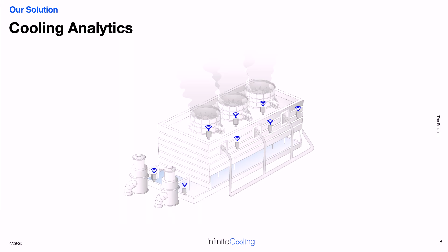We're addressing all of these issues in a couple of ways. Typically, our first step is we start with our cooling analytics product. The reason is we noticed there's very little monitoring done on these cooling towers, and as a consequence, literally every cooling tower we've ever seen was operating well below its optimal efficiency, just because they don't know what's going on in those systems. So we now sell a suite of sensors that can be added to these cooling towers, and we developed proprietary algorithms that use physics and machine learning to do real-time monitoring, optimization, and predictive maintenance. The main impact is energy savings, water savings, and usually most importantly, increased cooling capacity, so you can cool more with the same system.